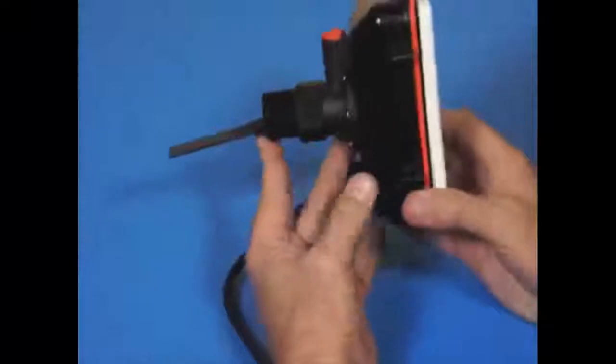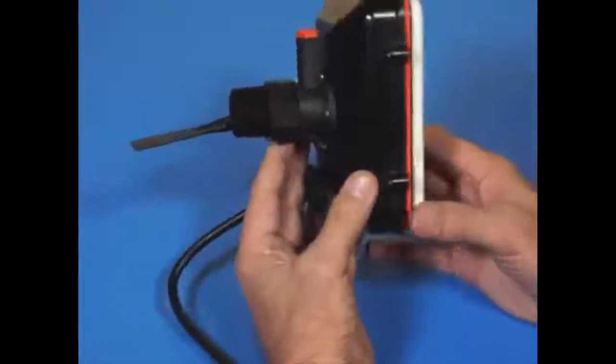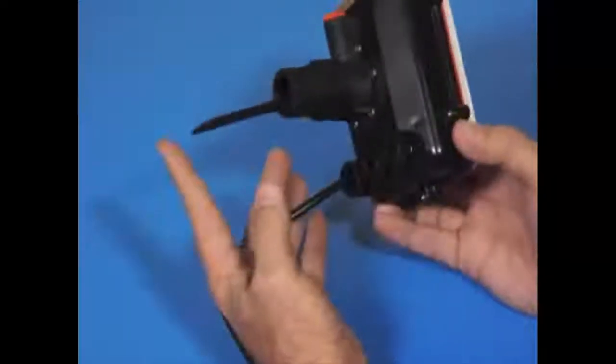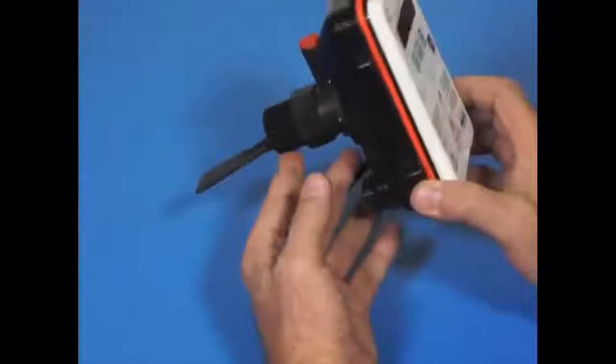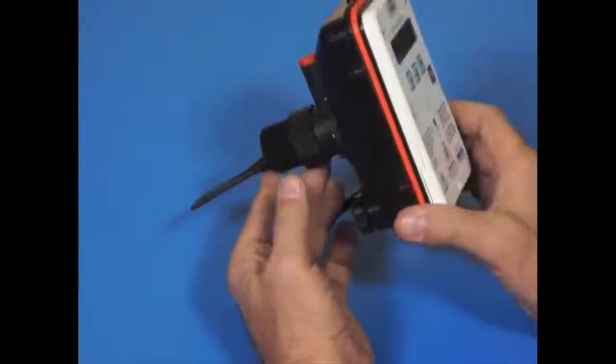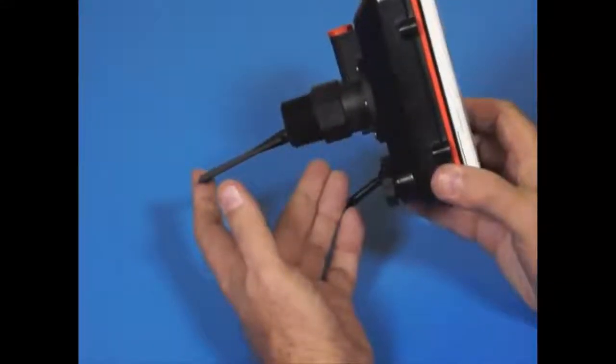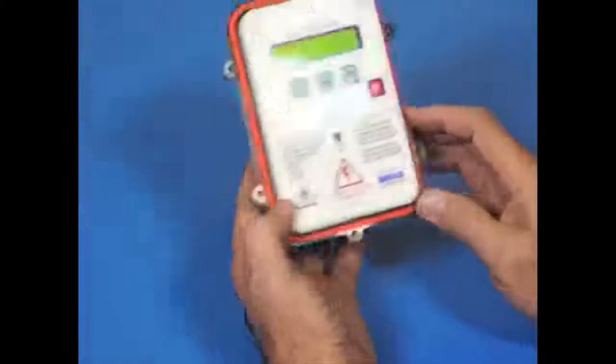In its most basic form the F29 is a simple override on start flow switch. It's able to start a pump up in spite of an initial lack of flow, wait till flow is established and then hand command over to its paddle and thereafter run, held on by the paddle. If flow is lost, the F29 detects the flow stopping and shuts the pump down.